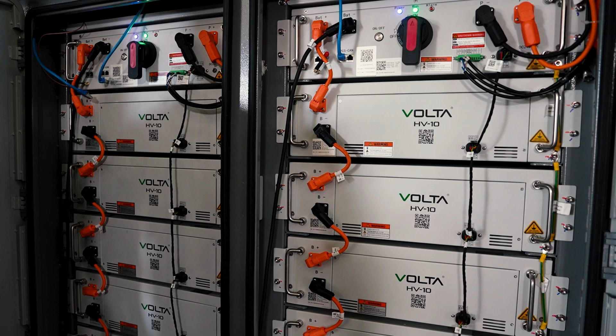All right, now the switching on process. Please unplug all your communication cables like it has come out of the box. First thing that you do is turn on your isolators. Wait for 5 to 10 seconds. Then you can switch on by pressing the silver buttons. You will hear all the relays click. Then your system is in 100% state. Plug in your communication cables, from your master battery from CAN to the second battery PCS. Done. That's your battery connections.